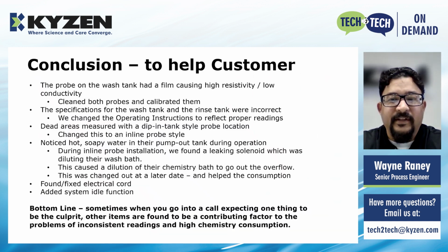So there were several things which helped this customer. We cleaned the probes and calibrated them, and after this they gave us the proper readings. We changed the set points and operating instructions. This gave better clarification. We installed an inline sensor instead of the dip style. This gave steady readings. We found a leaking solenoid. This lowered the chemistry consumption over time. We fixed an electric cord and made the system safer. We also added a system idle function, which will help lower chemistry consumption. So the bottom line is sometimes when you go in with a plan, you find other contributing factors to your problems.